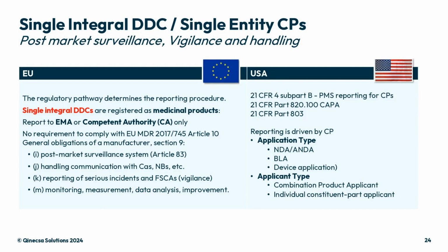There is, however, no clear recommendation of reporting of device complaints with potential impact of drug delivery between national competent authority where the notified body is located and the reference authority for the medicinal product. There is an assumption, or that's the practice so far, that the notified body and the national competent authority communicate any kind of issue with each other, and they do not require the manufacturer to do it themselves.